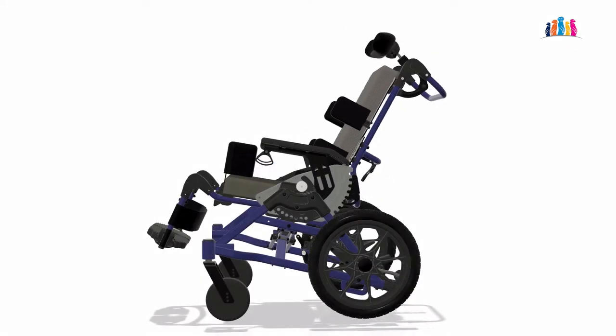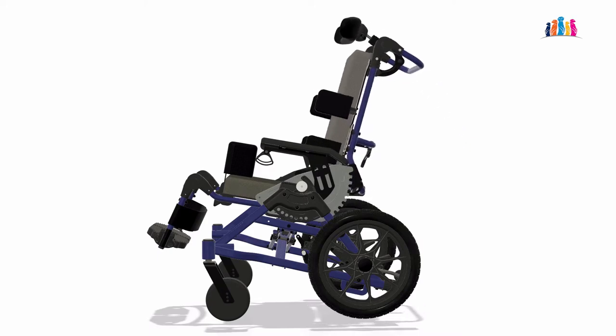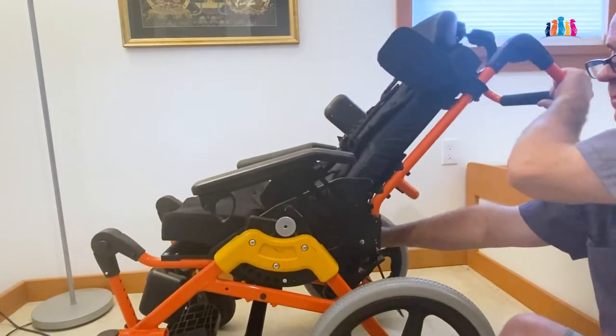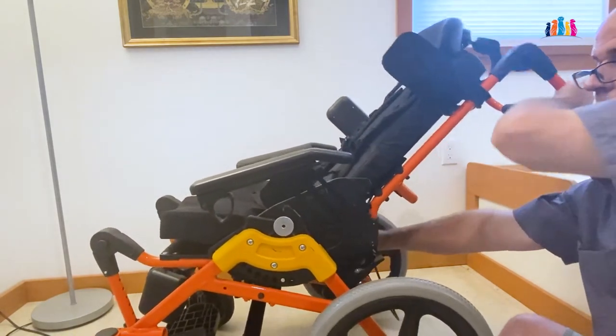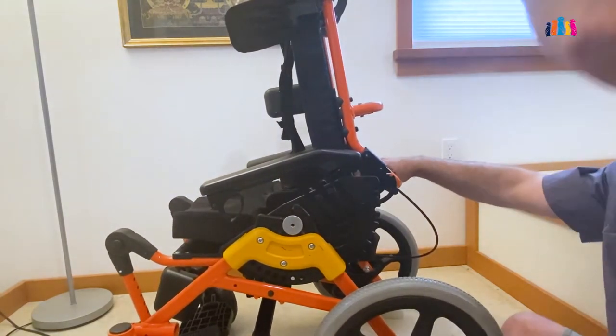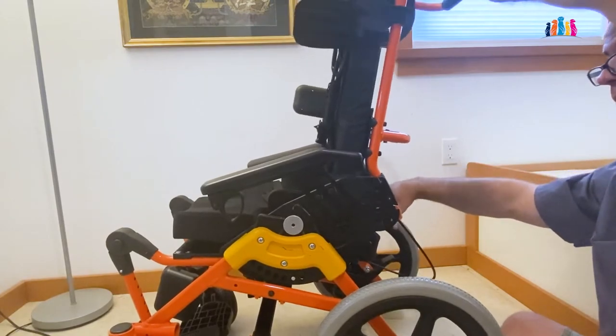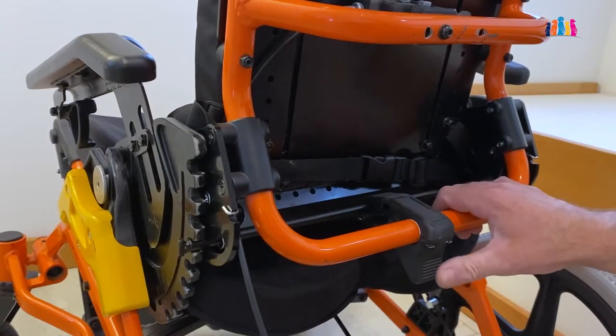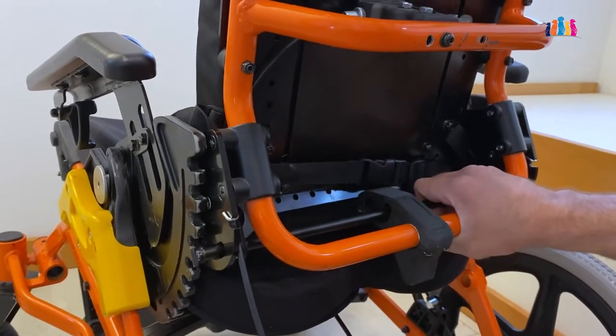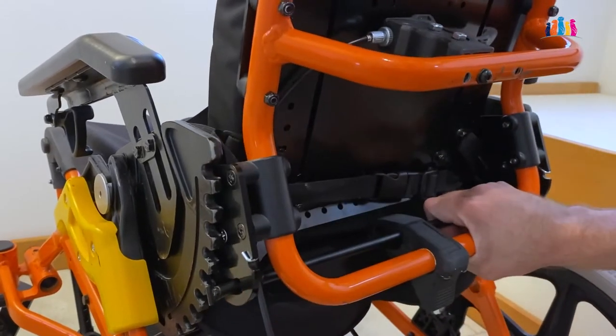Many clients require some degree of recline in their backrest. Please understand that changes in recline make significant changes in many other parts of the chair that could be harmful. CUB's recline angle can adjust from 75 degrees to 135 degrees. There are 7 incremental positions for this recline. We have developed a recline lock that will allow easy adjustment but also prevent accidental releases. Keep everybody safe from playing little brothers and sisters.